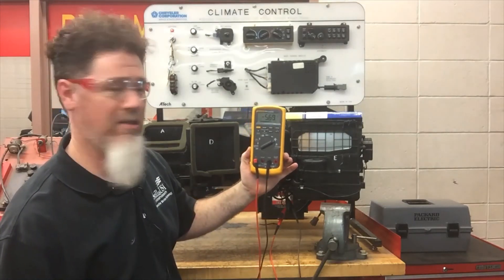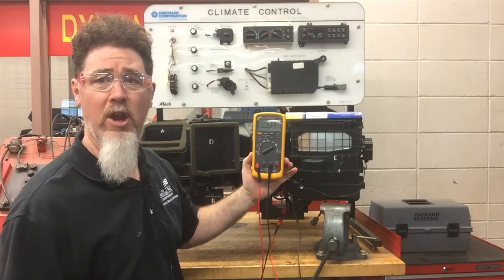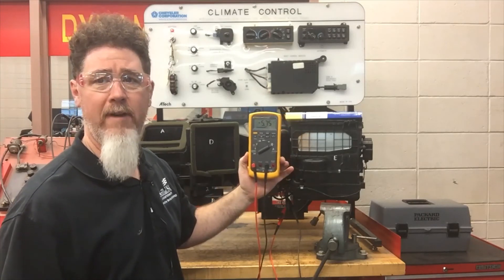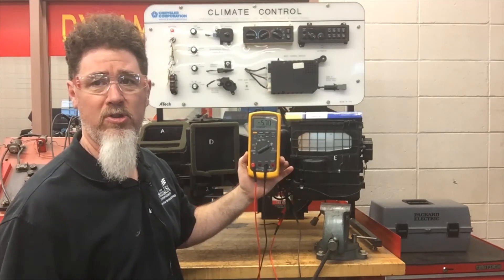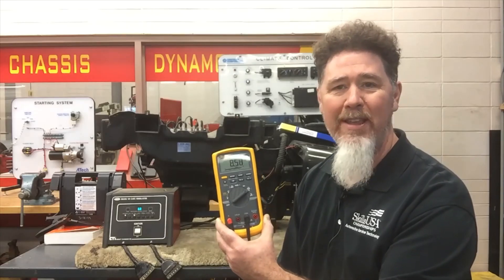One more time on the inlet side, which is more common. If I restrict it on the inlet side, the amperage drops down to 5.68–5.69 amps. There's less airflow going through the system, the fan doesn't have to work as hard, so there's less amperage on the fan.